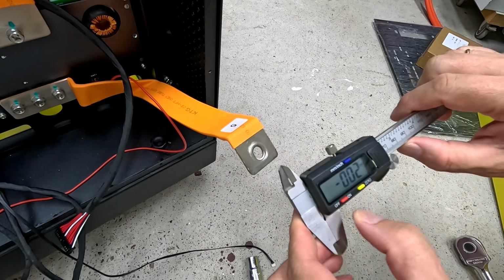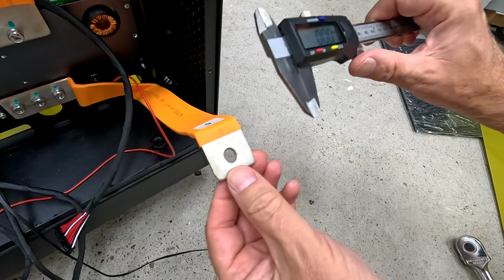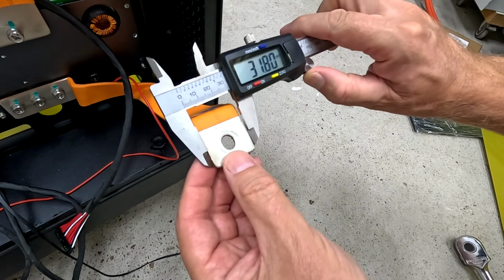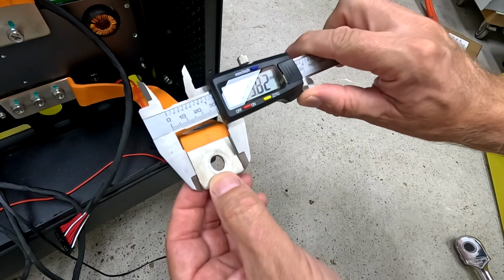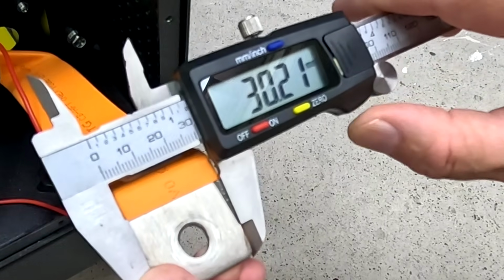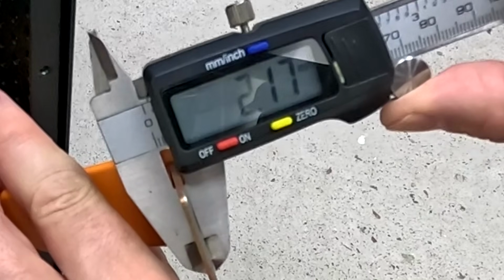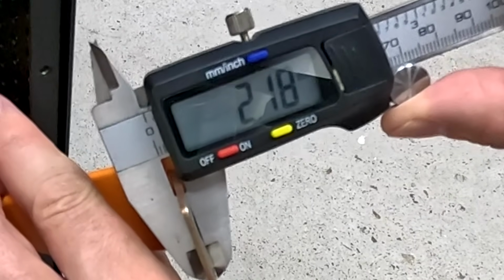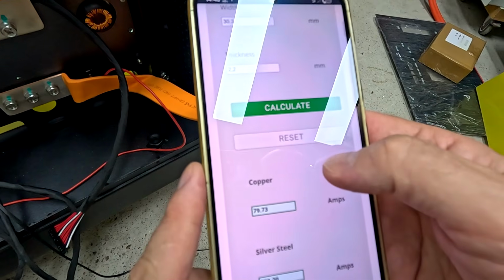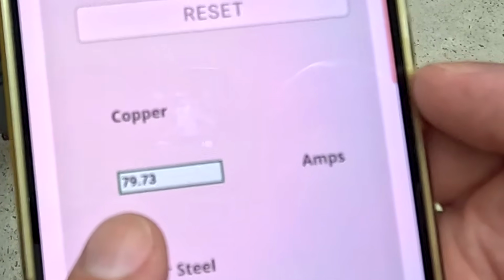So we also want to have a quick discussion about the bus bar sizes they have used here in this box. So the width is 30.2, thickness 2.1, 2.2. So when I put these numbers into a bus bar calculator, with copper we have an ampacity of 79 amps.